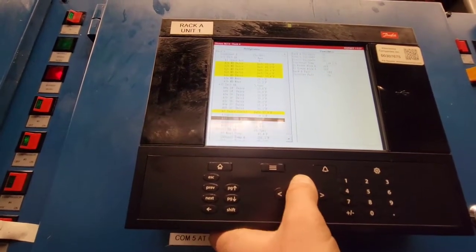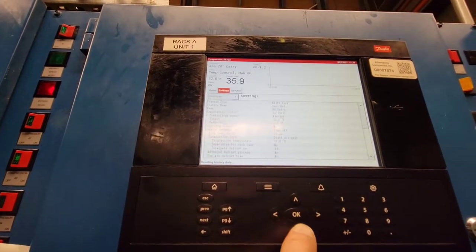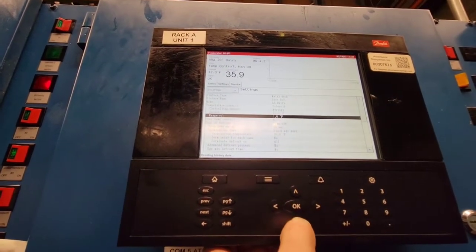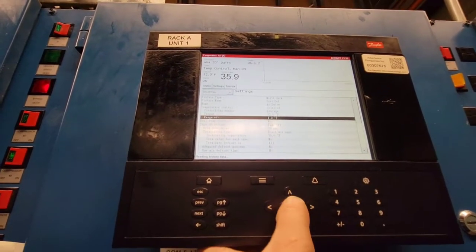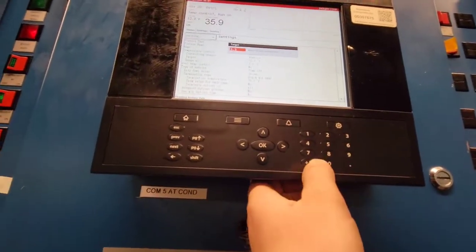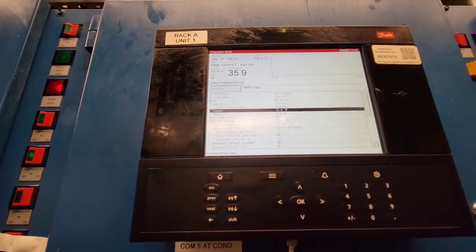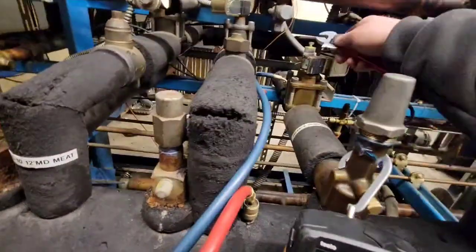Make sure that the A matches the B — pretty sure they do. Settings. The target is 32. The range is plus or minus one. It's a very tight range. So actually 33 would be fine because the range is so tight that it won't turn on — it'll stay running if it's 34. So 33 is actually fine.